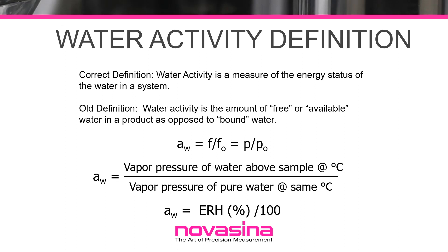Water activity is defined as the energy status of water in a system and is rooted in the fundamental laws of thermodynamics through Gibbs free energy equation. It represents the relative chemical potential energy of water as dictated by the surface, colligative, and capillary interactions in a matrix. Practically, it is measured as the partial vapor pressure of water in a headspace that is at equilibrium with the sample, divided by the saturated vapor pressure of water at the same temperature.